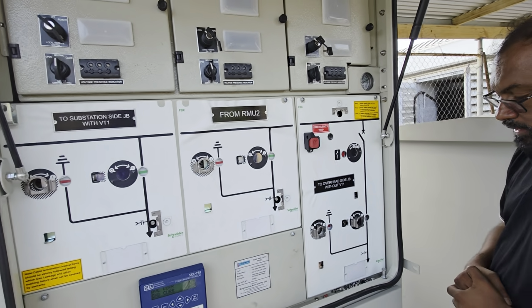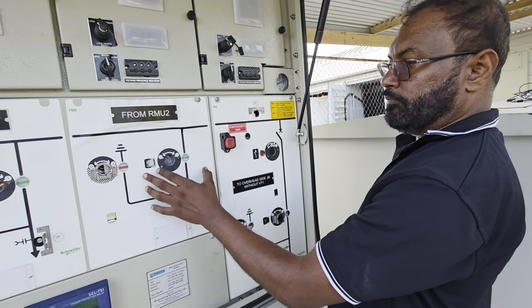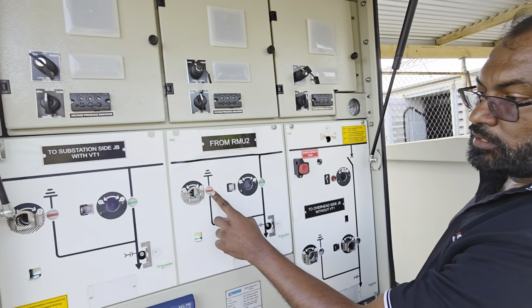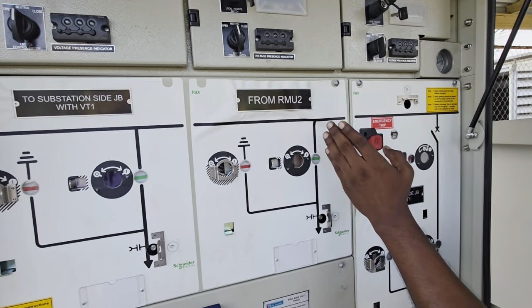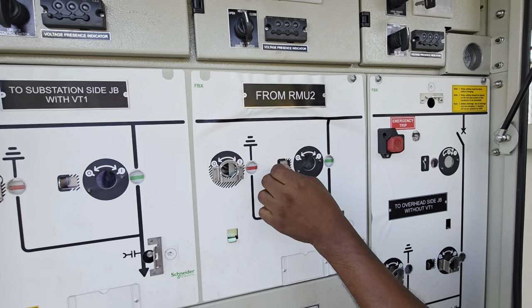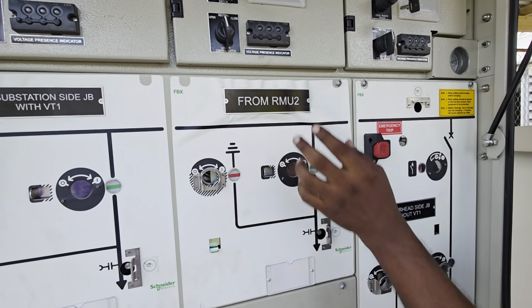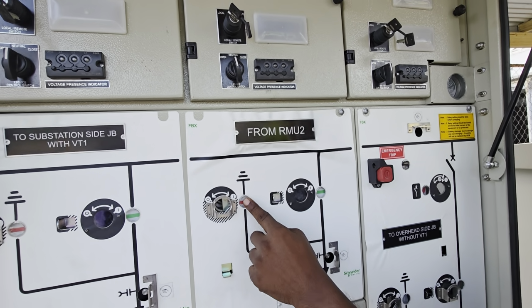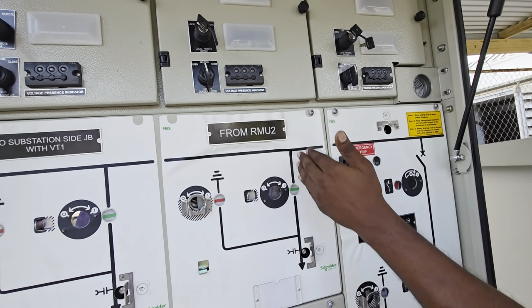Now another thing you'll notice: if this is earthed — at the moment it's not — you will not be able to close it no matter what, because of the mechanical interlock and also the electrical interlock. If this is earth, you can't close this.